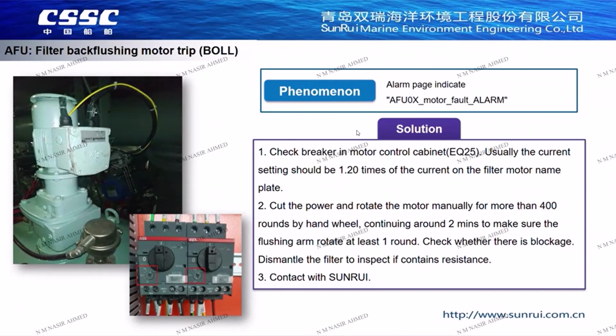Boll filter back flushing motor fault alarm. First, check the current breaker settings in the motor control cabinet. The current setting should be 1.2 times the motor rated current. If there is no problem with the breaker setting, the motor can be rotated 400 turns manually by the hand wheel, at which the back flushing arm moves one complete circle inside. Check if any resistance is felt. If necessary, disassemble the filter for inspection.